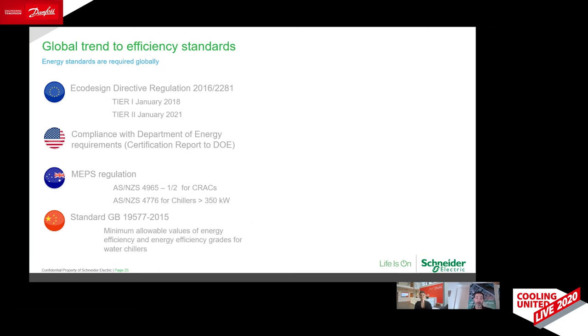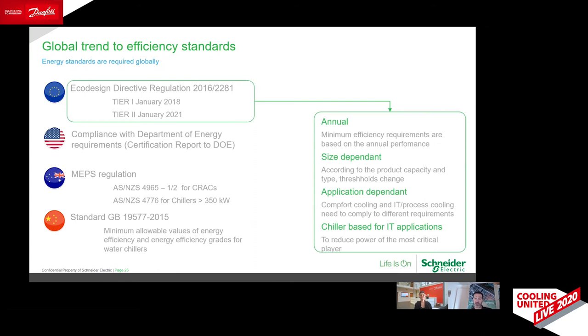So the European community with the Ecodesign directive, the first tier in 2018 and the new one on January 1st next year, decides and defines different efficiency requirements if you're looking at comfort cooling, process cooling, or data center. For data center, when the temperature exceeds 12 degrees Celsius, units are rated as efficient. When you look at process cooling, you need to look at the seasonal efficiency as the SEPR parameter. Then, when you're looking at comfort, there is the SEER, the seasonal energy efficiency ratio.